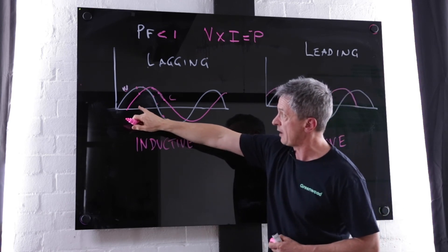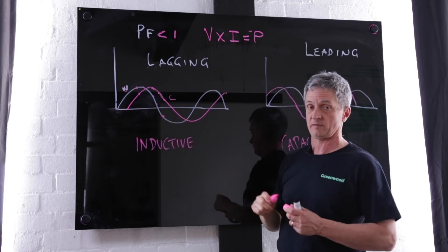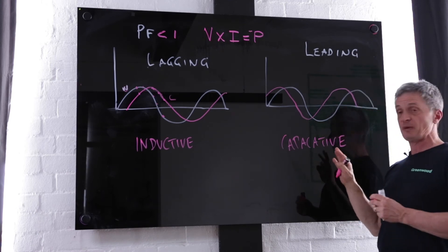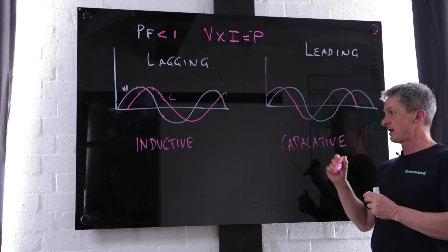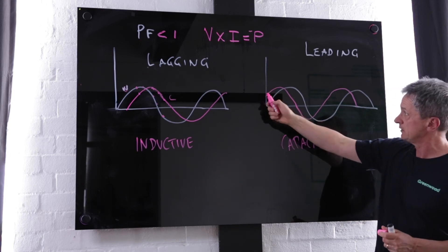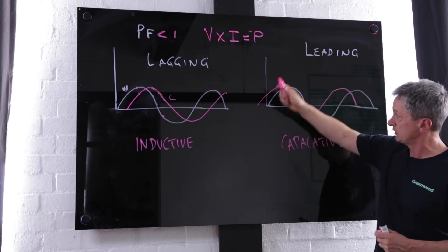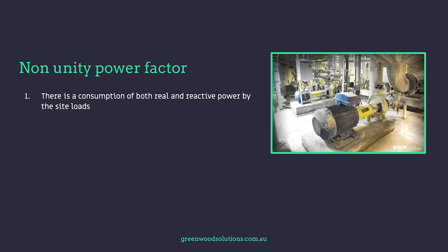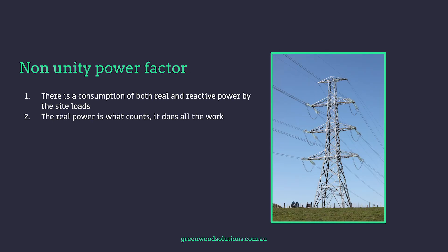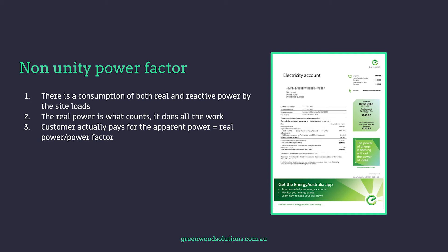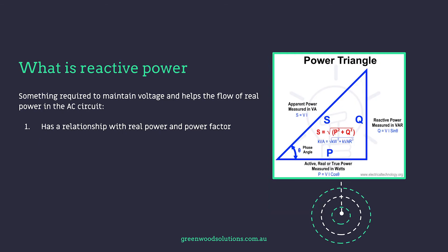The amount of reactive power is determined by how out of phase the current is from the voltage. In a site that has a capacitive scenario, it has a leading power factor — the current leads the voltage, but the same principle applies. In reality, there is a consumption of both real and reactive power by site loads. The real power is what counts — it does all the work. But the consumer actually pays for the apparent power, which is real power divided by the power factor. Reactive power has a relationship with real power and power factor.